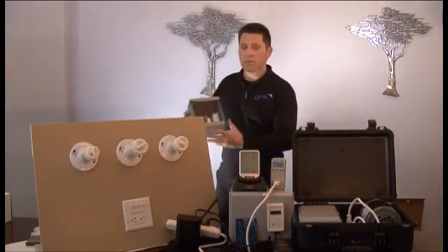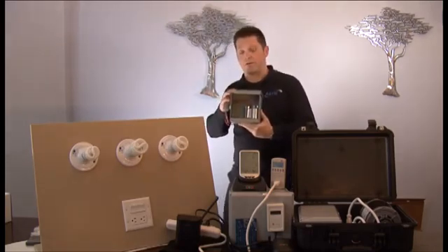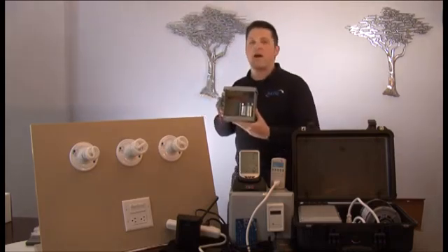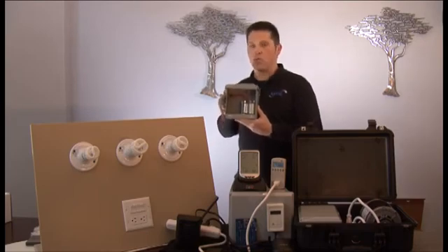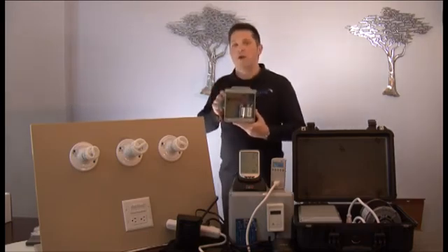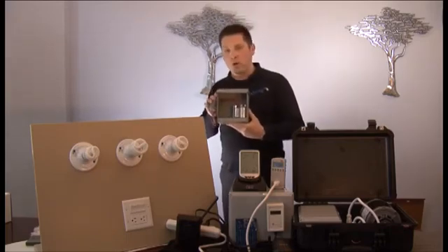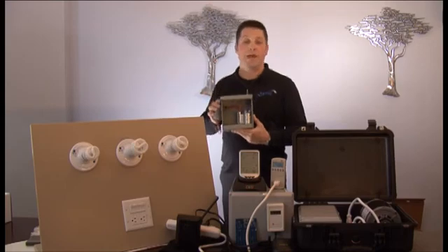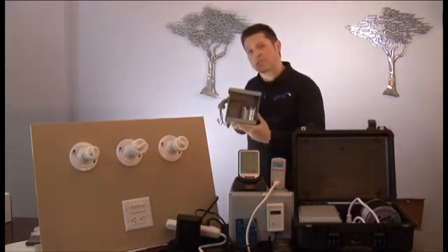Not to beat on this product, because there are applications where this product can be very effective. But what we see is two made in China, 35 microfarad metal dielectric run capacitors. This is 100-year-old technology that on the perfect motor would save some electricity while that motor was running. The minute that motor's not running, if this was on the load, it would actually increase your bill. How about that? It's also wired phase to phase.